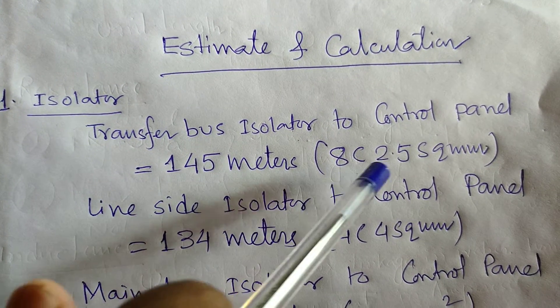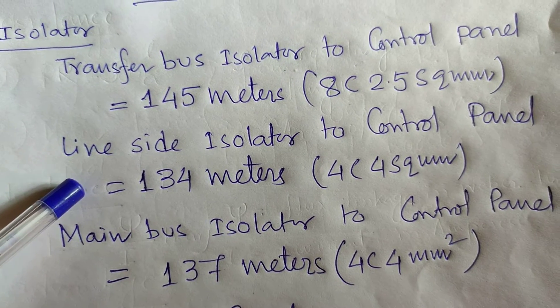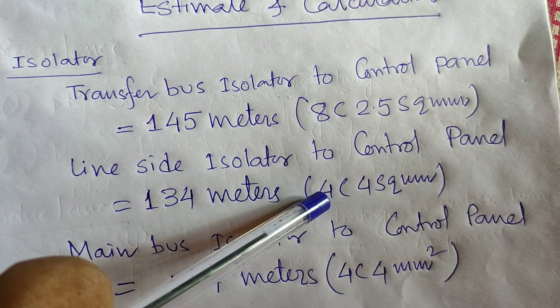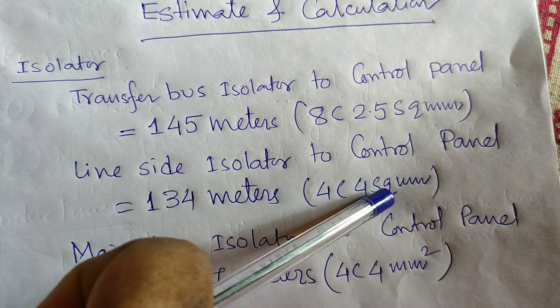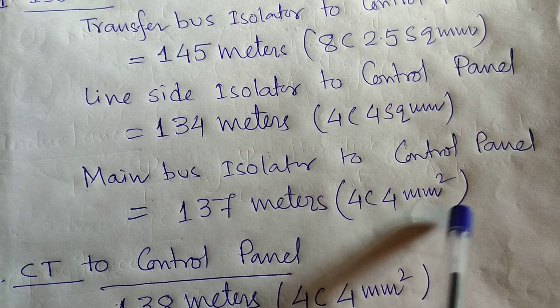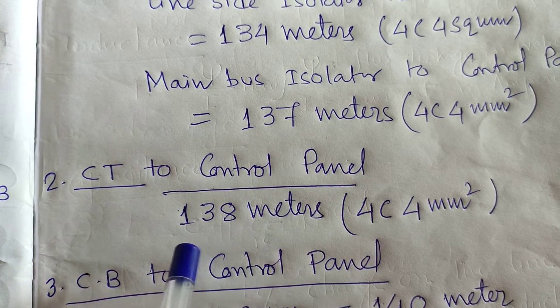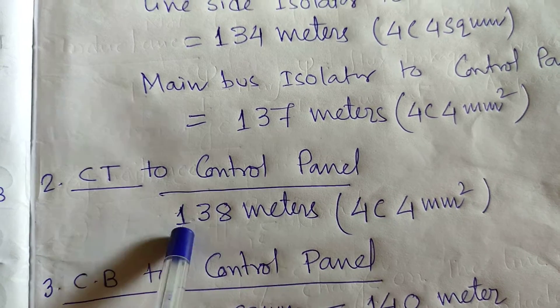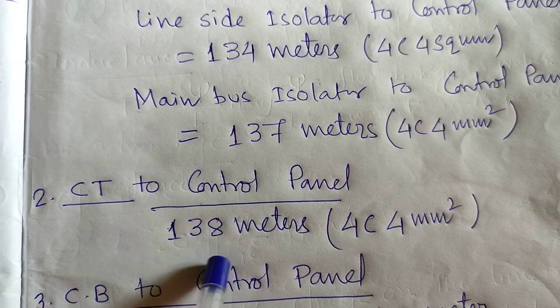For the line side isolator to control panel: 134 meters, four-core 4 sq mm. I am laying four-core 4 sq mm; you may also lay four-core 2.5 sq mm cable. Main bus isolator to the control panel: 137 meters, four-core 4 sq mm cable. For the CT to control panel: 138 meters, four-core 4 sq mm cable required — for my substation's case, newly erected 33 KV bay.